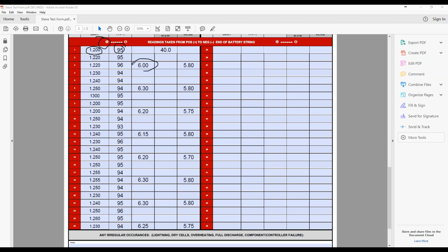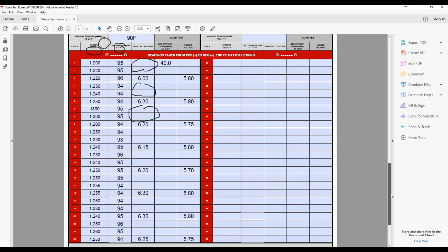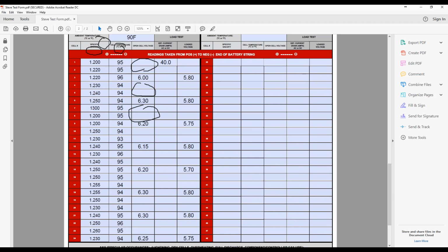And then, of course, we've got our individual battery voltage readings - this is battery voltage with no load, called open cell voltage. You'll want to measure that with no load individually, in the beginning, and then kick on some load. Give us an idea how much current you're running. If you're running 2,000 watts in a 48-volt bank, take 2,000 watts, divide it by 48 volts, that's 41 amps of current - put 41 amps of current there. You don't have to run it all the way down, you can just draw a line, 41 across the way.